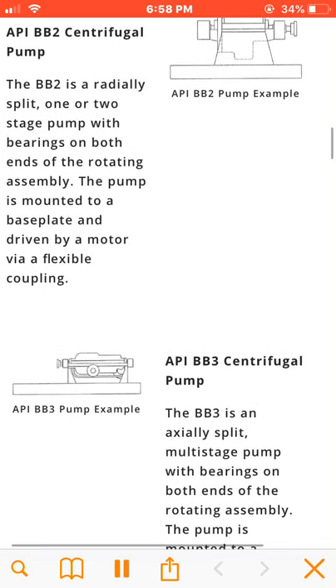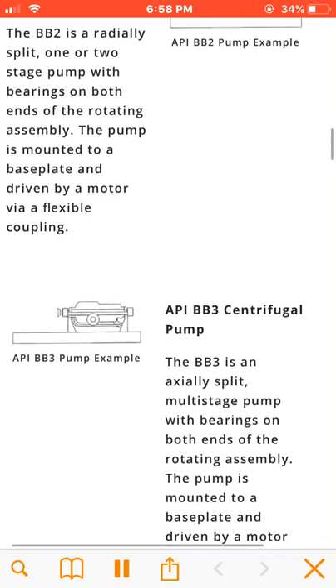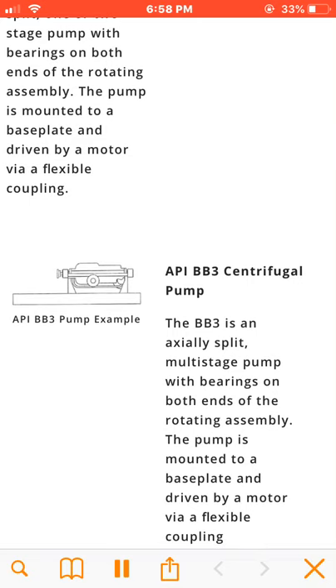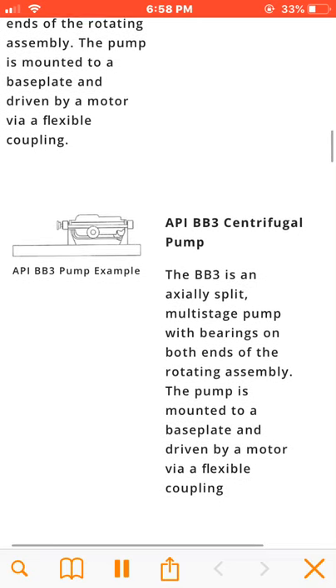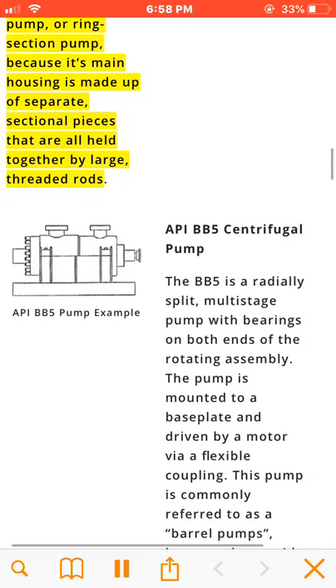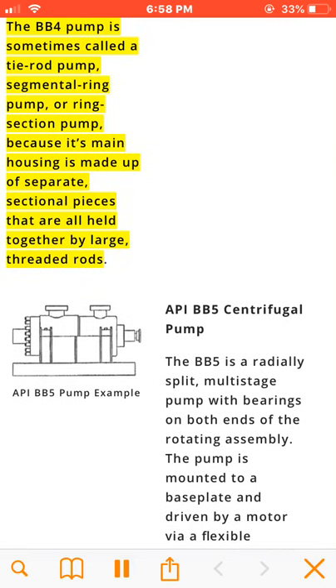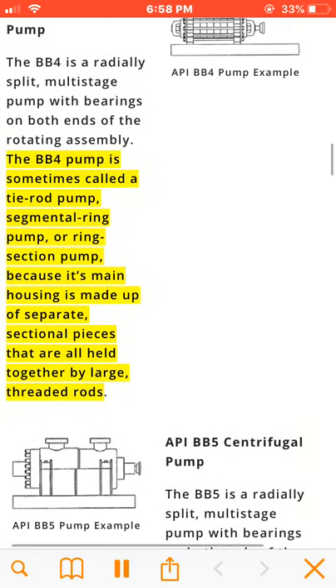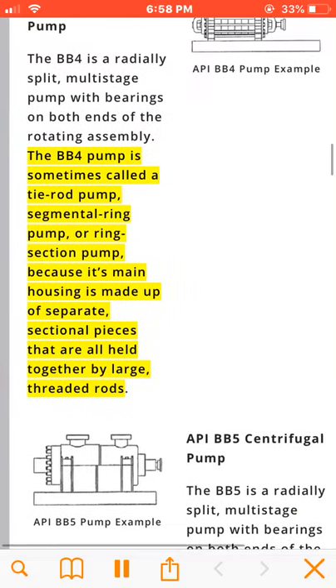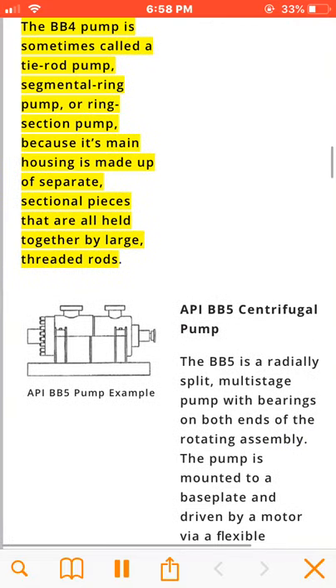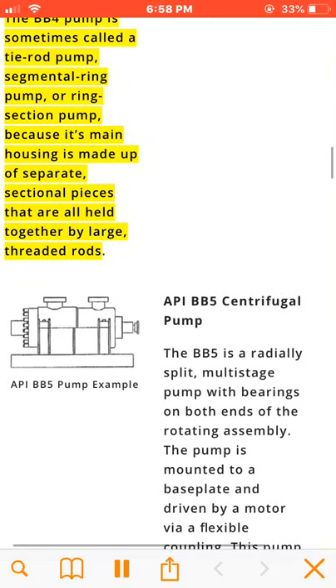The BB4 is a radially split, multistage pump with bearings on both ends of the rotating assembly. The BB4 pump is sometimes called a tie rod pump, segmental ring pump, or ring section pump, because its main housing is made up of separate sectional pieces that are all held together by large threaded rods.